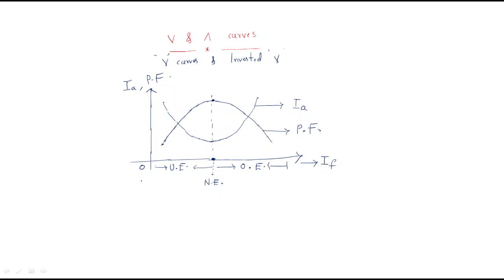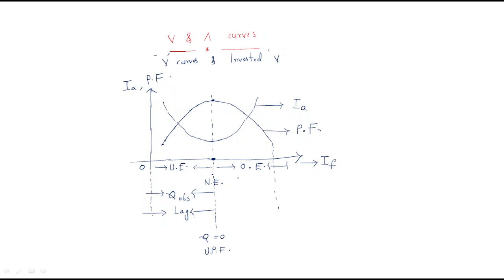At this point we can define additional parameters. In under excitation condition, the synchronous motor absorbs reactive power and operates at lagging power factor. At normal excitation, reactive power is zero — no absorption and no delivery — and it acts at unity power factor. In over excitation condition, reactive power is delivered and the motor acts at leading power factor.